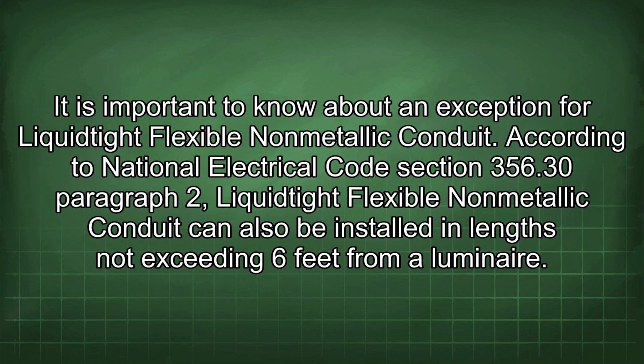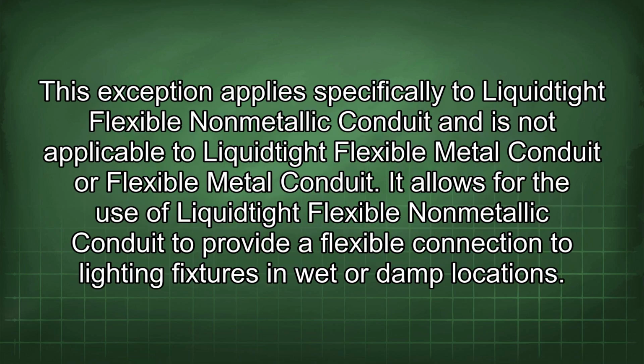It is important to know about an exception for liquid-tight flexible non-metallic conduit. According to National Electrical Code Section 356.30, paragraph 2, liquid-tight flexible non-metallic conduit can also be installed in lengths not exceeding 6 feet from a luminaire. This exception applies specifically to liquid-tight flexible non-metallic conduit and is not applicable to liquid-tight flexible metal conduit or flexible metal conduit. It allows for the use of liquid-tight flexible non-metallic conduit to provide a flexible connection to lighting fixtures in wet or damp locations.